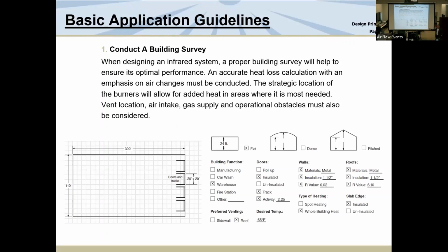An air change is, generally speaking, 50 to 70% of your heat demand in a building. And really, there's no real way to know what the air changes are. Now, maybe you can get an engineered system to make other stuff you do or know. But as a whole, when somebody calls and says, I've got a building that's 60 by 40, I've got a building that's 60 by 200, how much heat do I need to put into it? The primary driver is how many air changes are in the space.